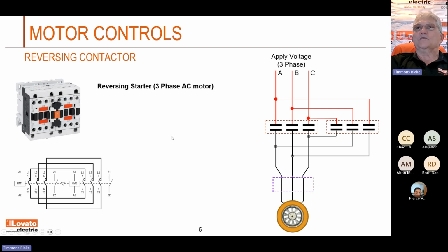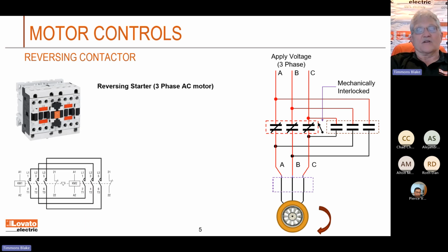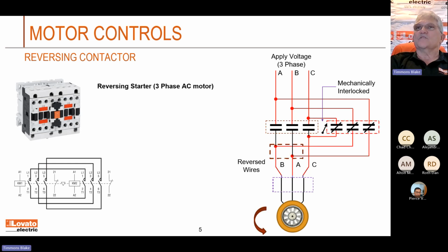You apply the voltage, and as soon as you apply the voltage, you'll start the motor turning. Then you want to turn it the other direction, but you can't because it's mechanically interlocked. You do not want both of those coming on at the same time. So we interlock these not only electrically but mechanically. Once you get it turned off, then you can switch it to the other side and turn it on. That's how a reversing contactor works.